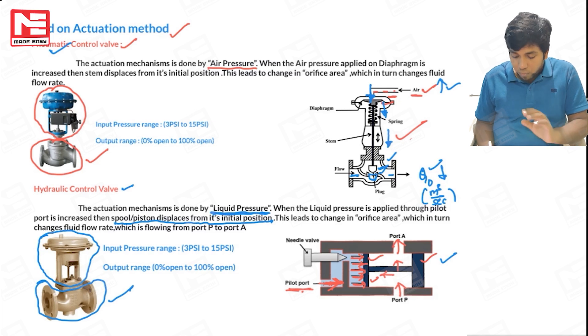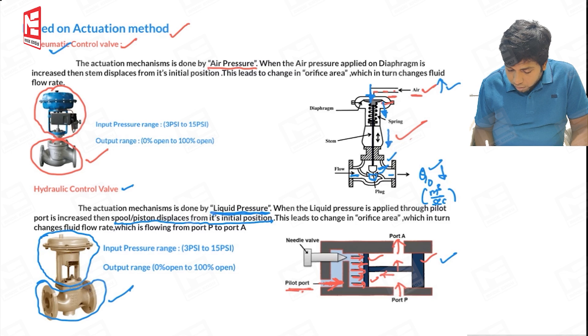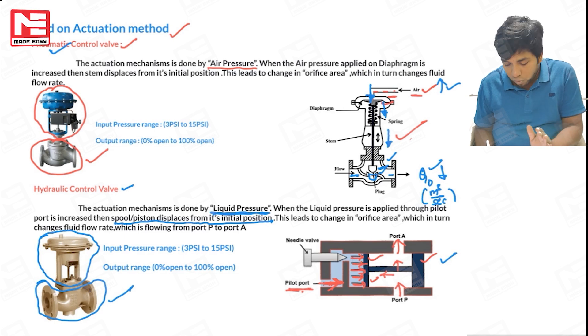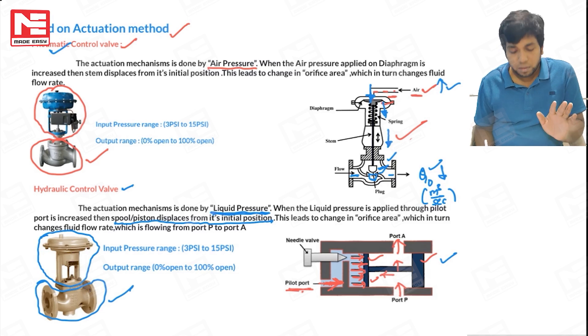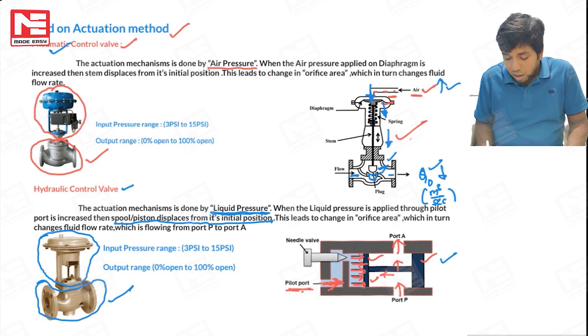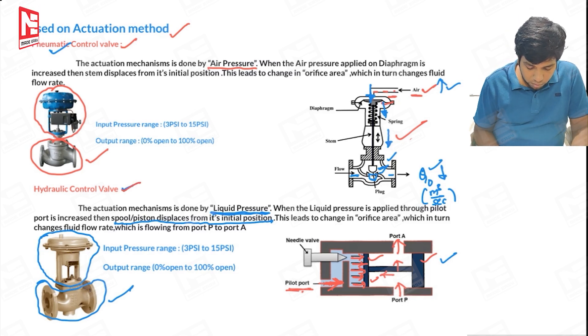To control the flow rate of the pilot fluid, a needle is provided. When you turn the needle it comes forward, controlling the flow rate of the fluid applied on the piston. If the needle is fully seated, no liquid can flow and there will be no pressure on the spool. Because the cylinder moves due to liquid pressure, this is called a hydraulic actuating mechanism, and the valve performing this action is called a hydraulic control valve.